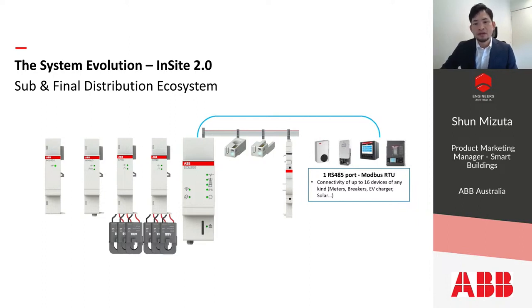Here, we have connectivity with Modbus RTU. InSite 2.0 can connect up to 16 Modbus devices, such as EV chargers, PV inverters, energy meters, or energy analyzers. Power analyzers are used to measure power factors, total harmonic distortion, or other power quality parameters. You can also connect to our MCCB or ACB through Modbus RTU.